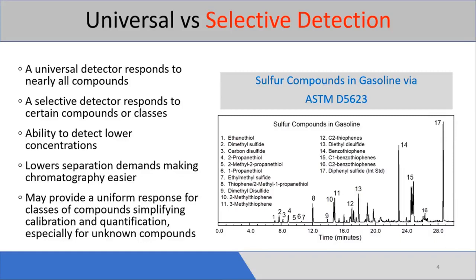Selective detectors may provide a uniform response for classes of compounds, simplifying calibration and quantification, especially for unknown compounds. The chromatogram on the right is from the analysis of a gasoline sample that contained 30 parts per million of sulfur. Even though we might not be able to identify each individual compound, we can obtain a measure of the total sulfur in the sample by summing the response from all peaks, and of course we can quantify each peak individually.